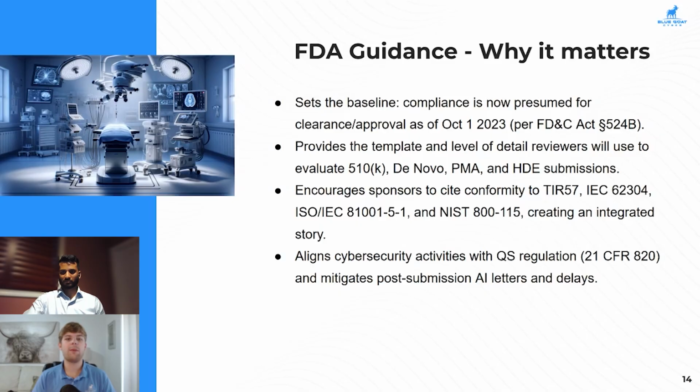Now, this is encouraging device manufacturers to cite conformity to all of these standards that we talked about. Of course, this isn't a comprehensive list of any of the standards that can apply to a medical device, but looking at some of these standards that we've mentioned, TIR 57, 62304, 81001, 800-115, these are all great things to reference as part of your submission materials. Now, this also talks about cybersecurity activities in alignment with quality regulations, and compliance with the standard is going to reduce the risk of getting a delay as part of any additional information letters, the risk of having a non-substantially equivalent letter from the FDA.